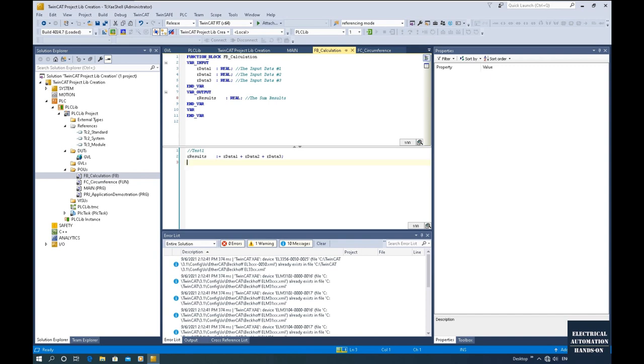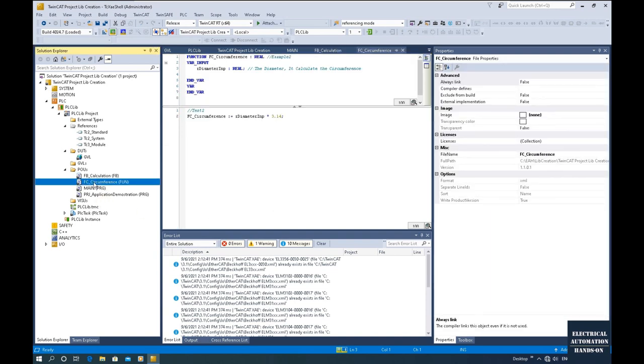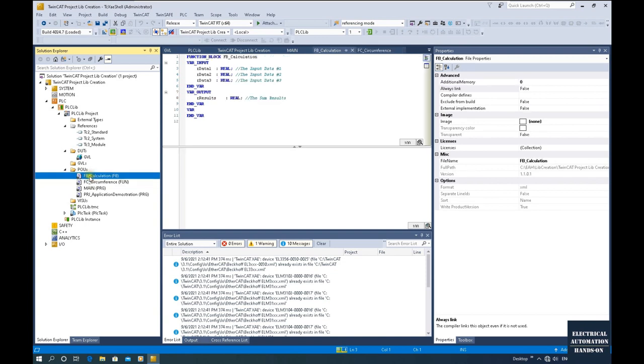Without comments it's really hard to figure out how to use a function or function block — we will show this later. Also, I highly recommend when you name your function or function block, you write a prefix so you know the role of that. Because when you import them as a library, it's a little hard to figure out whether it's a function or function block and how to use it. So I highly recommend you write a prefix.